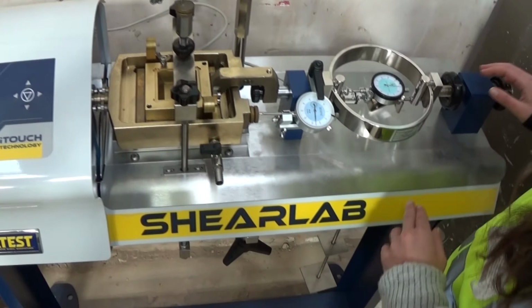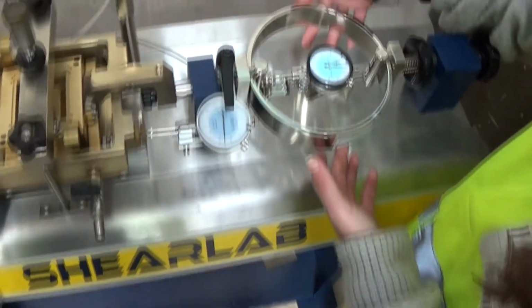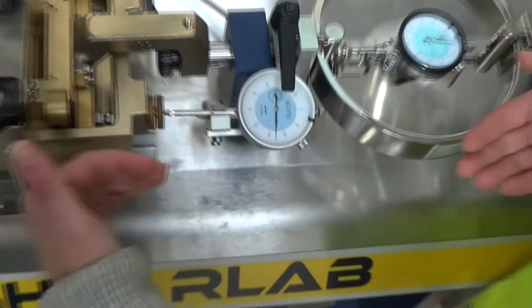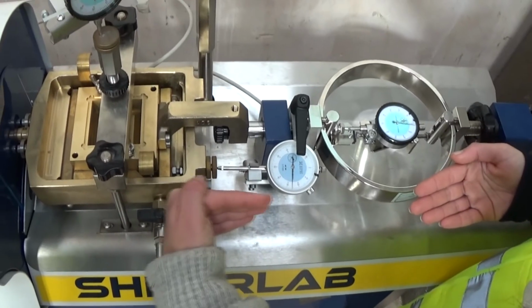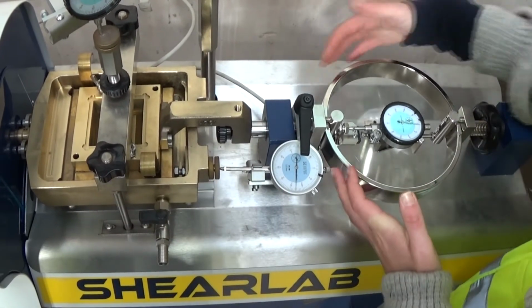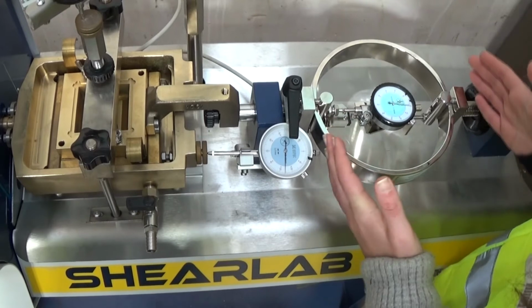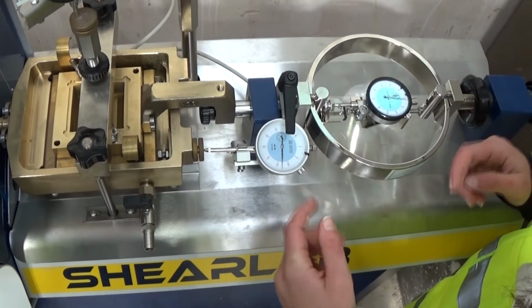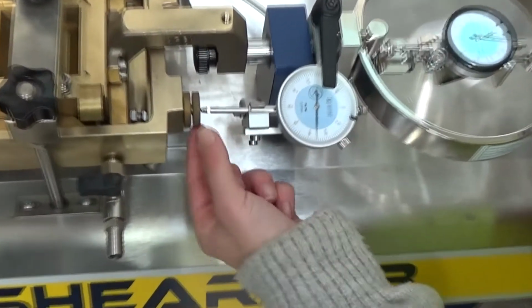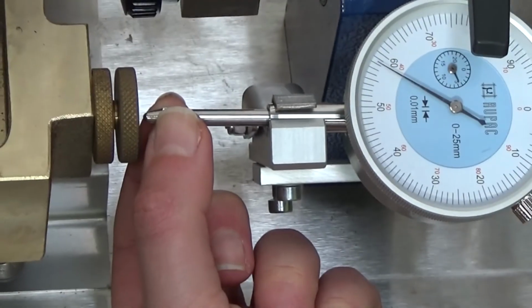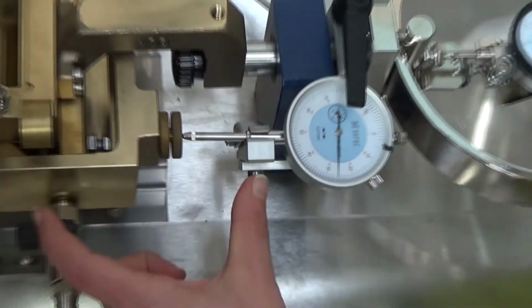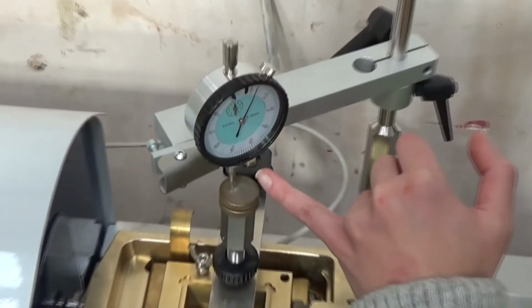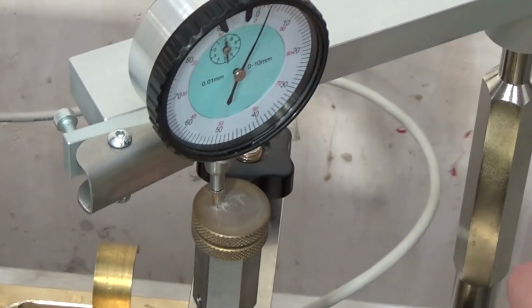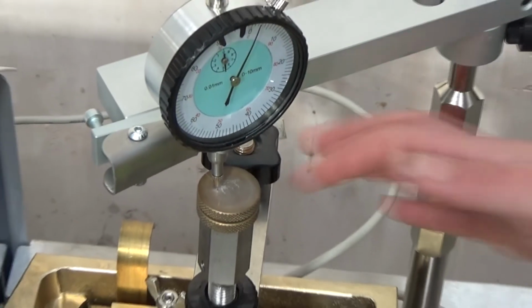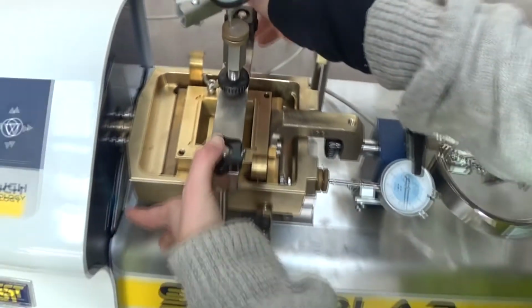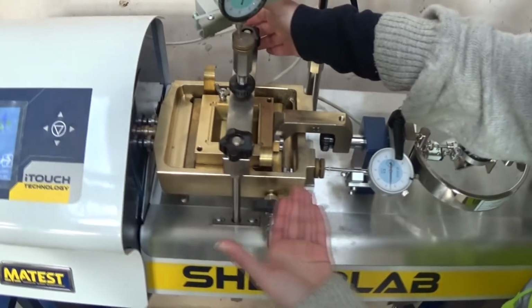And as I said, it's equipped with a load ring, so that during the shear movement, during the horizontal movement, the load ring will increase its value, and at the same time the dial gauge will record the movement of the carriage. The dial gauge in vertical direction is fixed because this system is fixed. It's always this one that is moving.